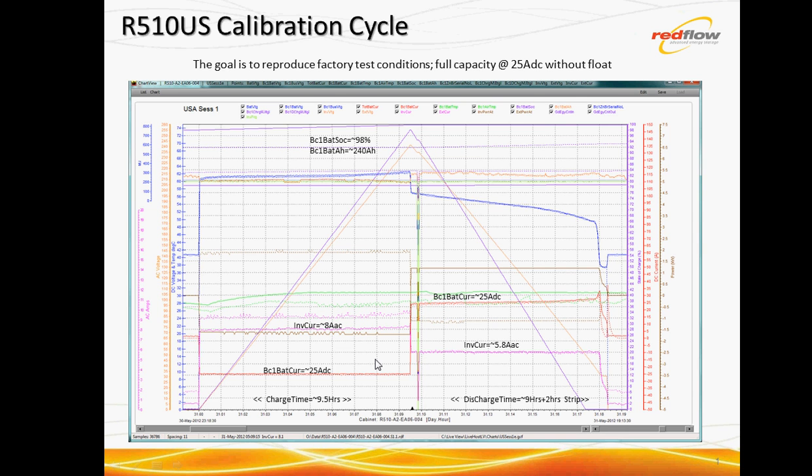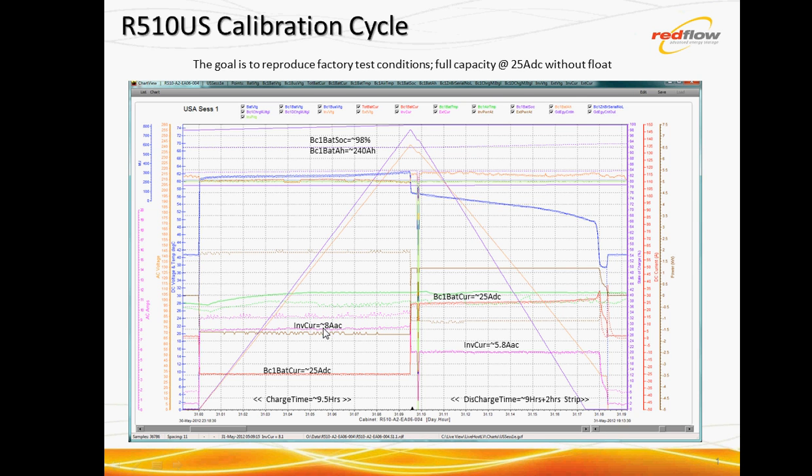So how are you going to achieve that? Well, we want 25 amps DC charging the battery. At the nominal US grid voltages, this one here around 210, 213 or so, we need to select 8 amps AC as the inverter current in the power control. And there, a cycle duration of nine and a half hours.